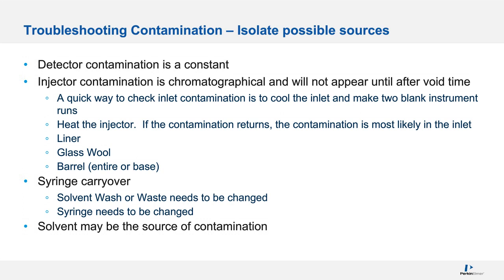Septa on the autosampler. That's why I never double dip, especially with an ECD, because ECDs pick this up. What happens is the syringe inserts that piece of septa into the vial, and methylene chloride or hexane leaches out whatever is in that material and gives contamination. So people, especially with ECDs, don't double dip. What I mean is use the same vial. So if you want to do precision, you set up 6 vials instead of 6 injections in 1 vial.